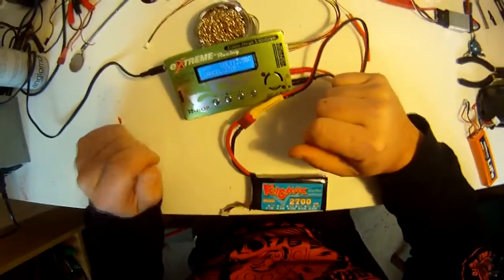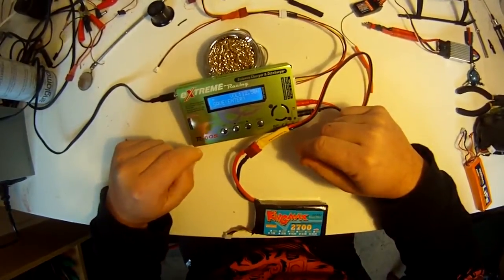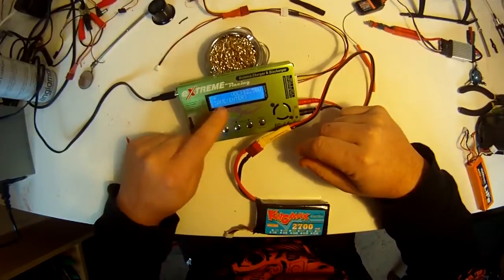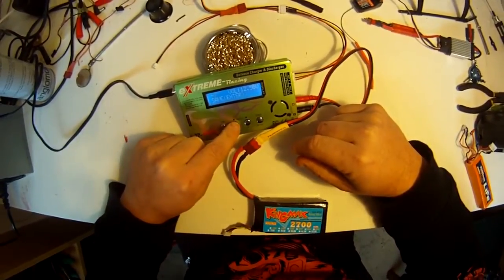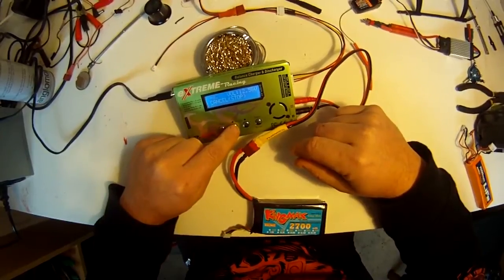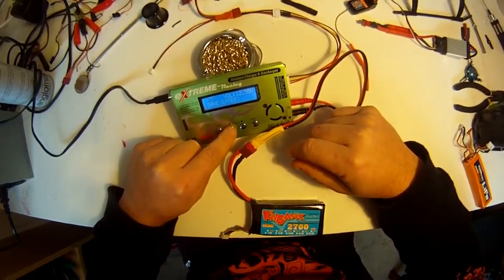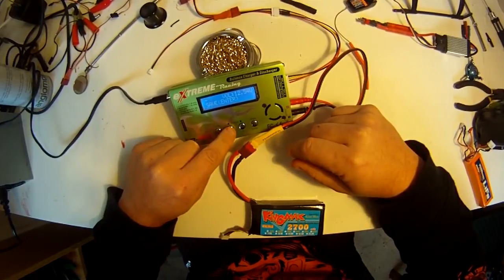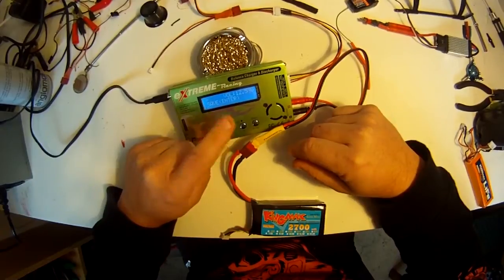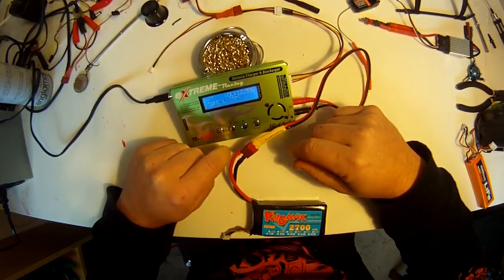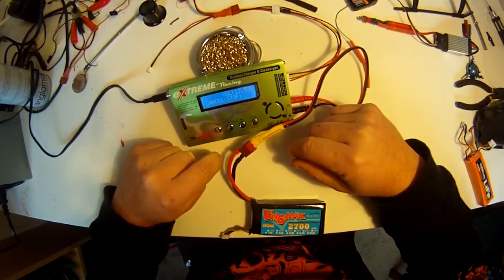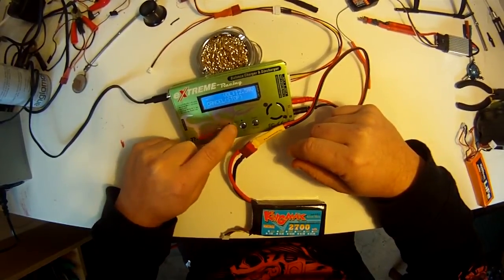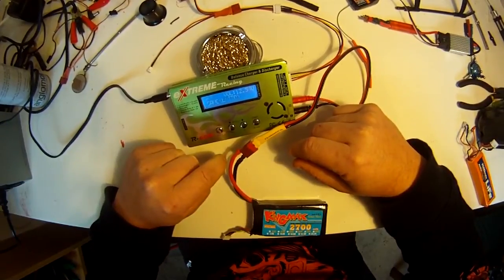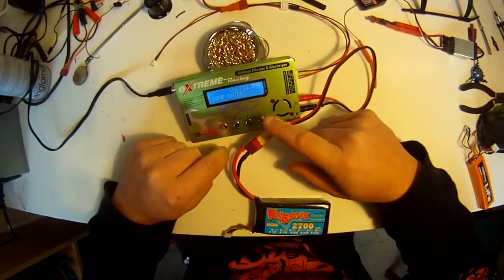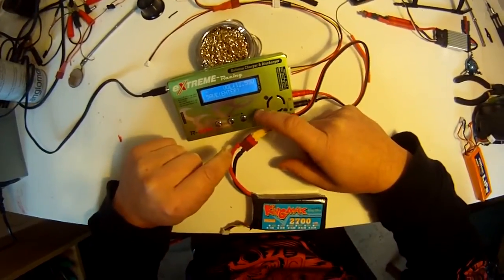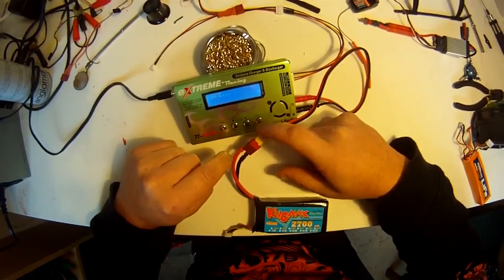And we've got 12.58. Now if you remember before we had 12.54, so what we need to do is hit the minus button to bring the calibration down a little bit. Just take it slowly down until it goes to 12.54 and sits there. If it sits there on it, yep, that's perfect - 12.53, 12.54, that's pretty good. Maybe take it up one, get it sitting solidly. Okay, that's going up the other way, so I'd rather put it down one a little bit - that's pretty good. Once you've got your calibration reading, hit start and hold to save, then release, and that's done.